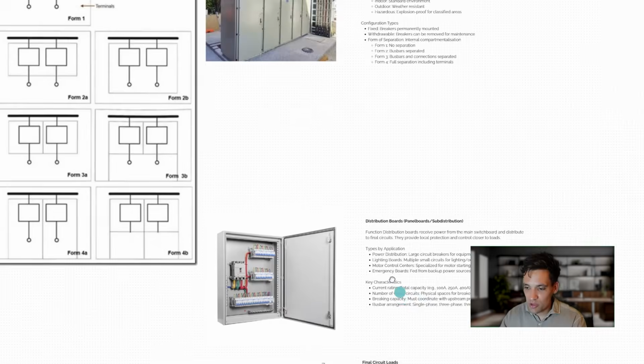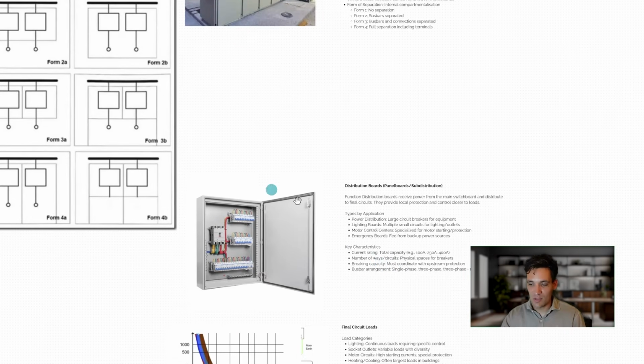So distribution boards, again, they operate very similar. They're very similar to main switchboards. They're just a lot smaller, that they're used for actually connecting the final appliances, so power distribution, lighting. You could have specialist motor control centers if you're connecting to pumps, or you could have emergency boards that have separate backup UPS or power supplies connected to them. Again, same key characteristics. We've got the current rating, we've got the number of incoming and outgoing circuits, we've got the breaking capacity, and we've got this bus bar arrangement in the form of the distribution board.